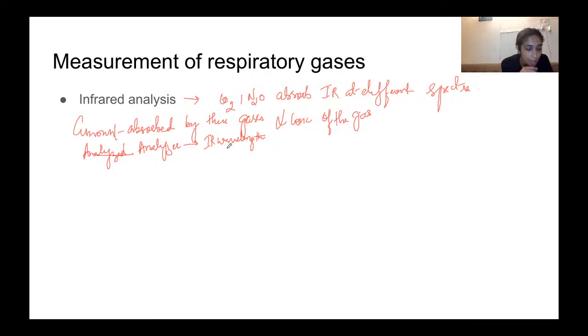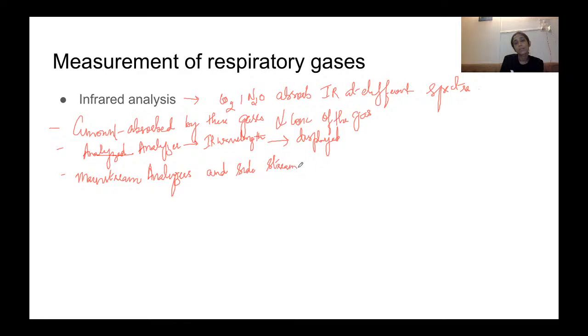So the analyzer will select the infrared wavelength, and most units used today can recognize the agent that is fed in. The purpose of the analyzer is to recognize the infrared wavelength, and this will then be displayed. So basically, what are the advantages of this? Infrared analyzers can be of two types: mainstream analyzers and side stream analyzers.